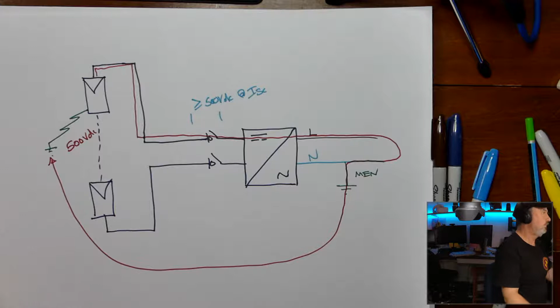Joe? I might add to that a little bit, actually. That's just got me thinking. For example, on a DC coupled system anyway, actually I think it still applies to AC coupled, in the event that there's a fault to PV voltage on the battery side, so if you get the conductor that's not the common in the actual power conversion equipment, which in ours, for example, would be the negative conductor, if that had a fault to earth, you'd effectively get the PV voltage on the battery side of the system.